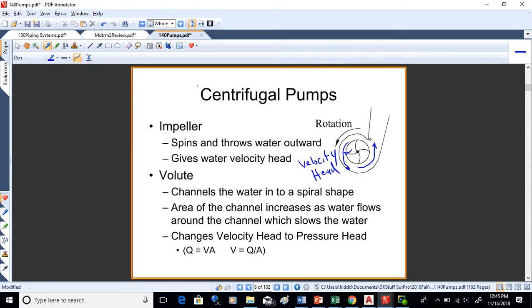When that impeller throws the water out, the water has what's called velocity head. But as it comes around, that channel starts to get bigger, so using v equals Q over A, the water slows down. That velocity head changes into what you want, which is pressure head. The volutes are intentionally in a spiral shape to increase the area and slow the water down, so velocity head changes into pressure head. The impeller spins and gives the water velocity head.